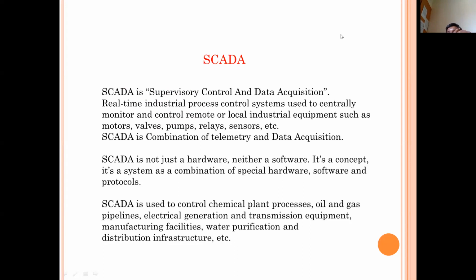This SCADA, either it can be a PLC or it can be a remote terminal unit. So what is a remote terminal unit? Actually, the remote terminal unit is similar to the PLC, but it has some advantages over the PLC. The PLC you need to program with ladder logic, or other types of programming available in the PLC. According to the IEC 61131, you have 5 programming languages, programming techniques that can be used for programming the PLC.